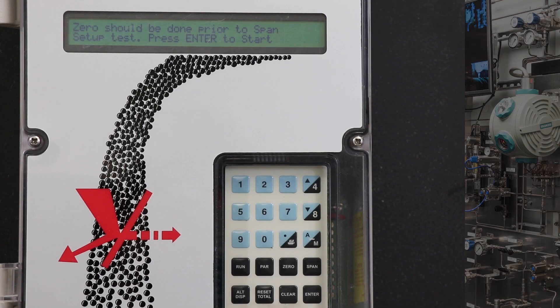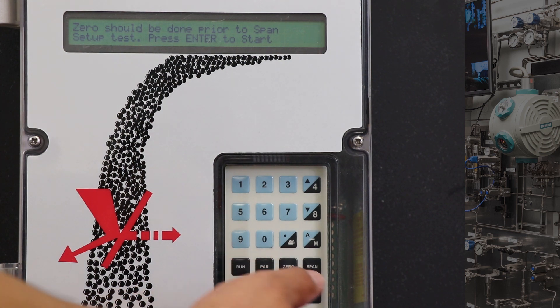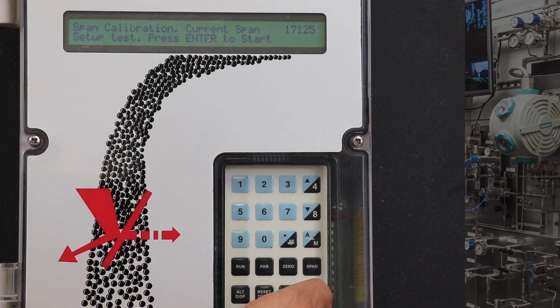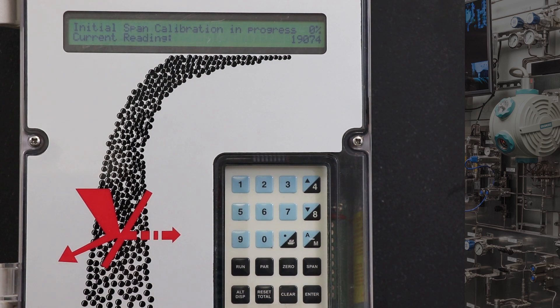Now we will start the span calibration by hitting the span button on the SF500. After this, hit the enter button. Please note, if it is a new unit, it will force you to do an initial span calibration. After initial span, you'll want to do two to three routine spans to make sure it repeats.